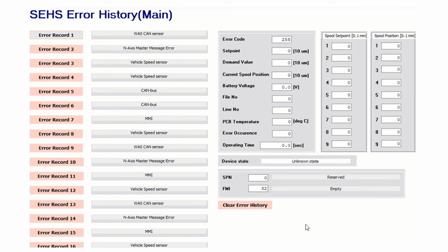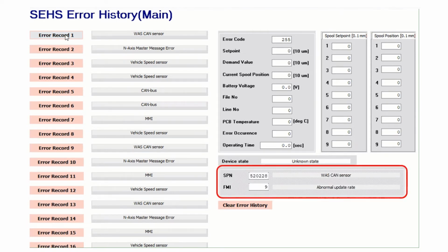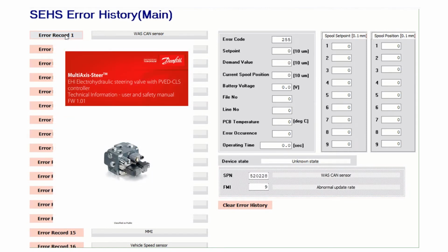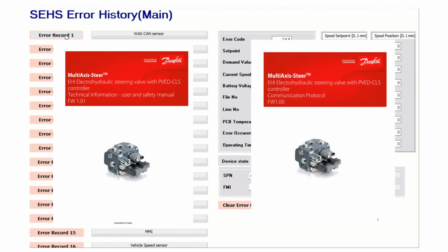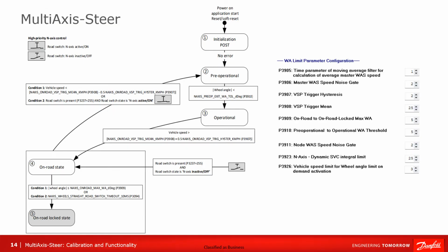The error history page can be used to find and diagnose errors that occur. Clicking on the error record button will cause an error code to appear, which can be identified using the multi-axis technical information. Another helpful document is the multi-axis communication protocol, which can be used to break down the raw CAN messages from the machine. The state machine diagram shows what parameters are used to control the transition to and from the different multi-axis states. For the slave axis to change from pre-operational to operational, the error between the wheel angle and wheel angle set point must be less than the value set by P3910. This is used to avoid surprise movement, especially during startup.